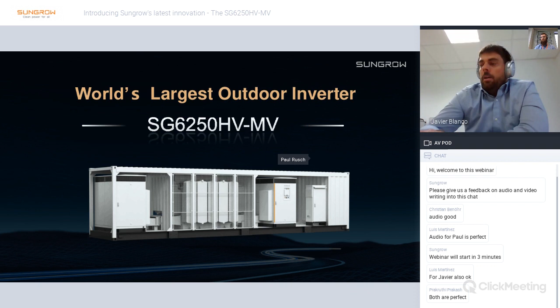Even when the station is containerized, all the components are designed for outdoor environment. The MV station is composed of an all-in-one solution built up with two SG3125HV-30 central inverters, the new version of central inverters Sungrow is launching this year. The solution comes together with an MV transformer plus RMU, making it a 100% plug-and-play solution built in the factory — just DC wiring and MV-AC wiring have to be connected to this station to make it fully operative.